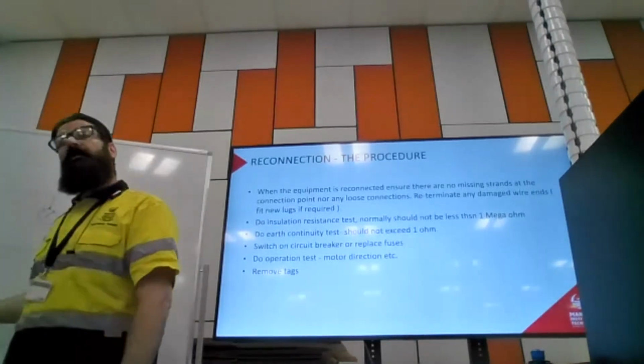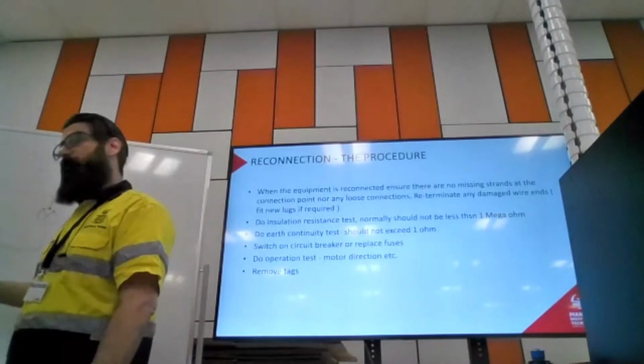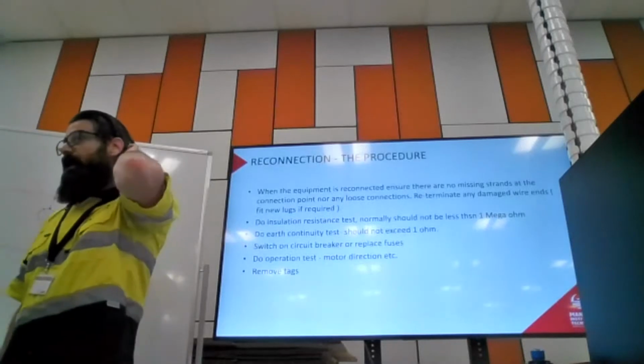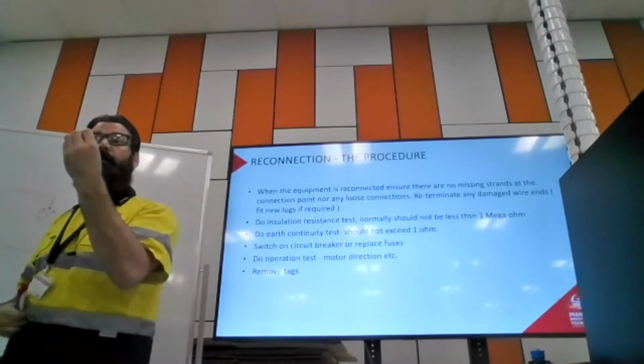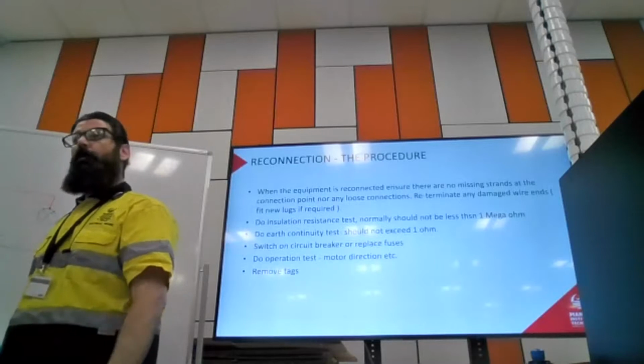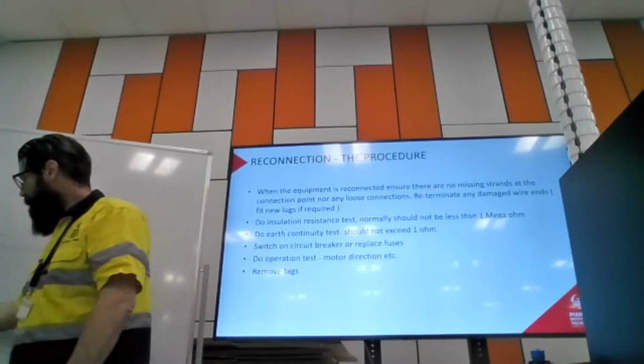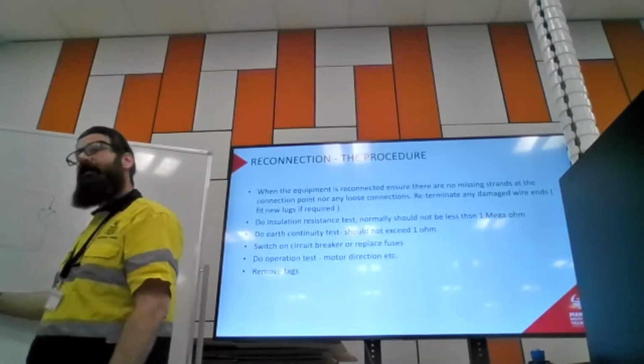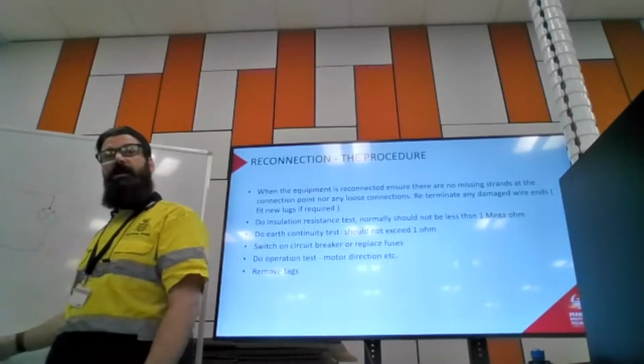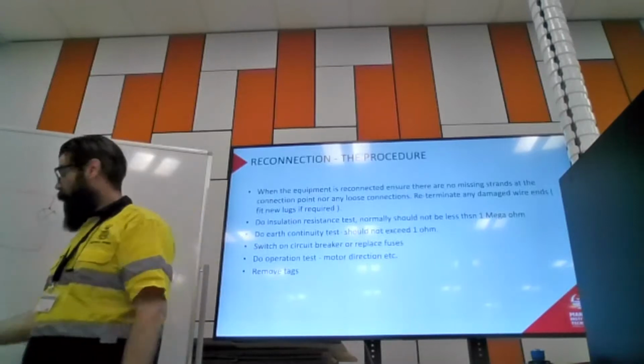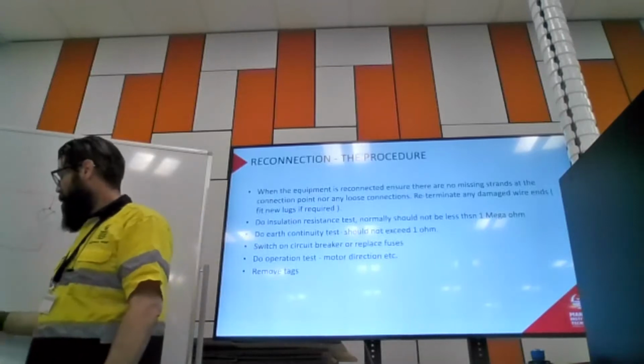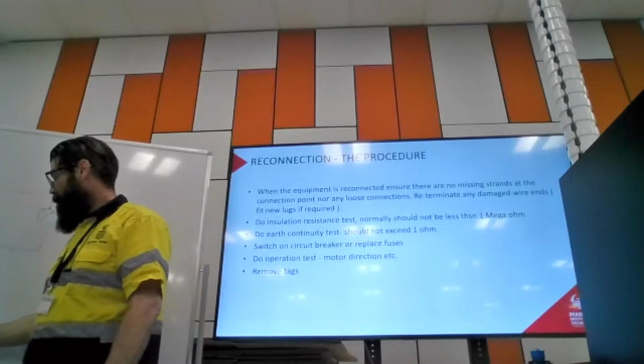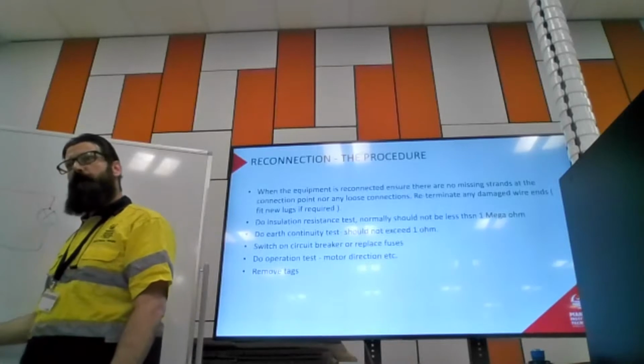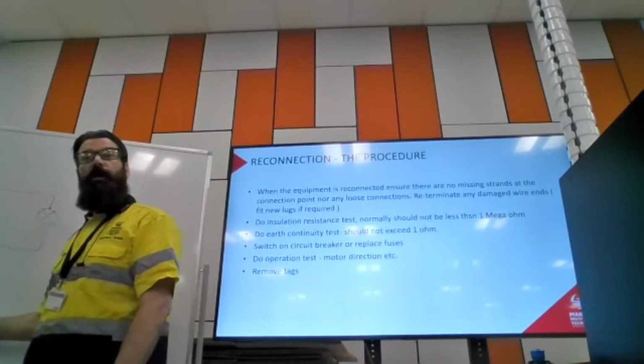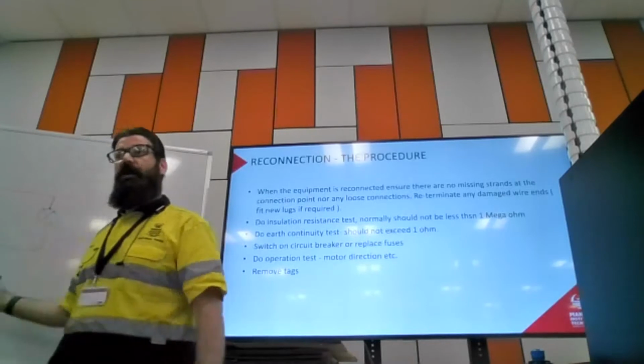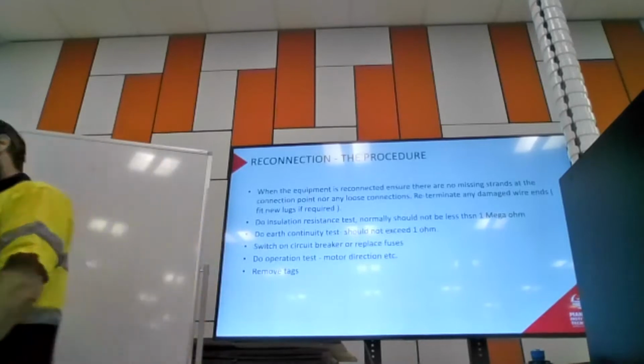The one downside of that magnesium oxide, particularly in water heating elements, is that it is quite hygroscopic. So it will absorb water. So any sort of perforation, even a tiny one in that outer sheath, which will allow a little bit of water in, could cause the water to go through to the center. And then we've got an earth fault, right? We're going to fail our insulation resistance test.